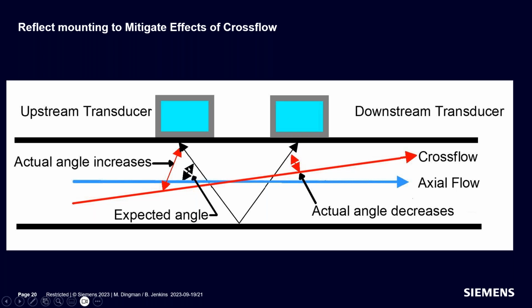Okay, so having the transducers in reflect mount, and this is the primary benefit of reflect mount. The error that you see on the left side of the screen is offset by the error on the right side of the screen. So the actual angle that we get on the one side is offset by the actual angle on the other side. So they cancel one another. And as a result, a large error, an error that's potentially 4% for every 1 degree out of plane that flow profile is, gets reduced to essentially nothing because of the averaging of the 2 paths.